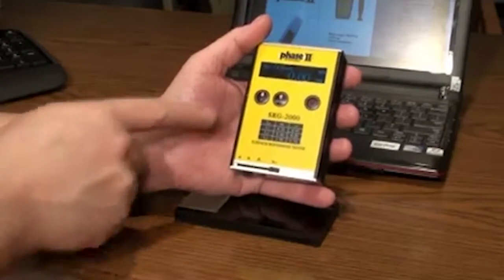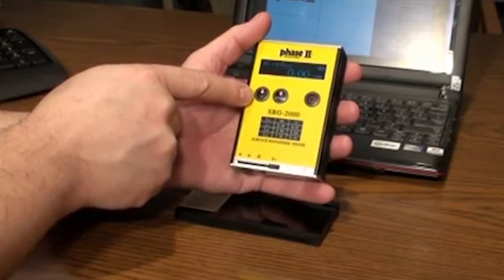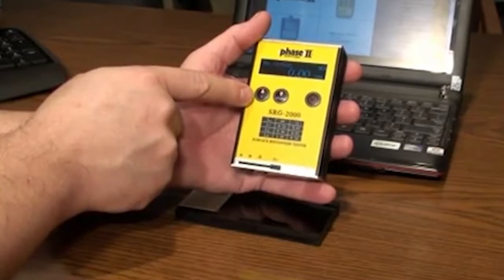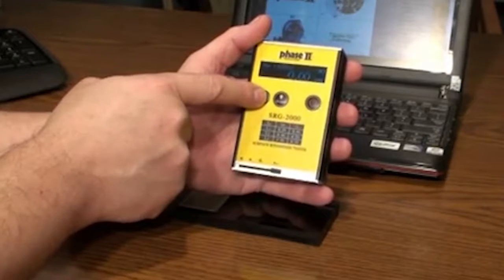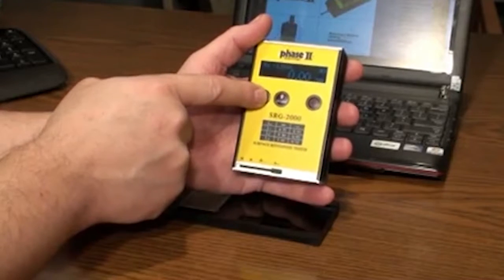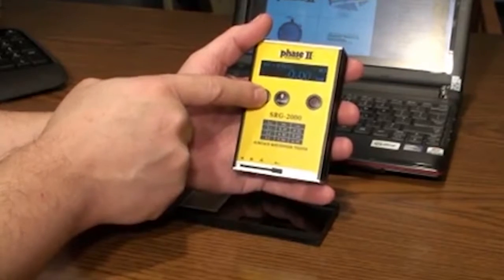The P button allows for the selection of parameter. This model is able to test in four different parameters: RA, RZ, RQ, and RT.